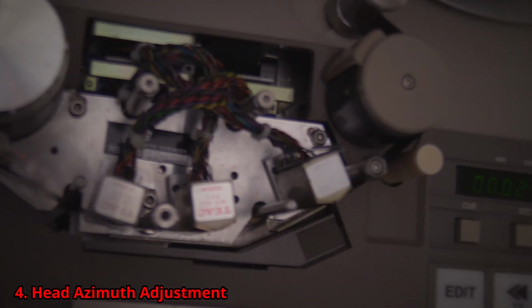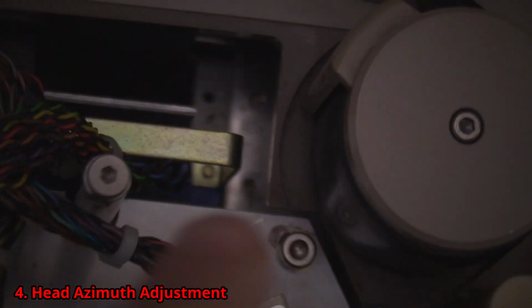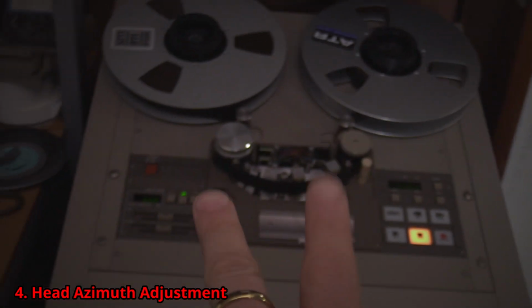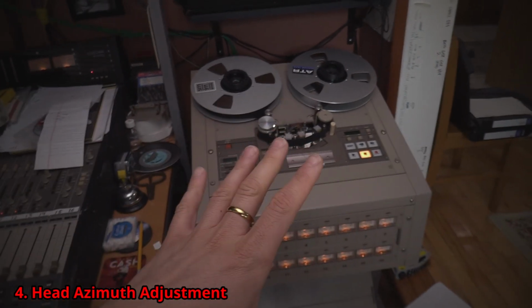And reminder here, just to show you, I am adjusting. Let's focus. There are 2 hex heads here, and that's where my Allen key is. I'm going to be tightening and loosening both those set screws to angle the head one way or another. I'm making really small adjustments. You've got to remind yourself that this adjustment is really minute. We're not making vast adjustments. I'm just doing that for the sake of explaining it. It's really precise measurements, changes here.